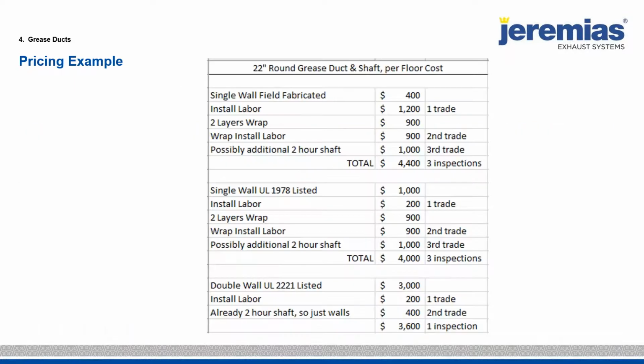The UL listed grease duct manufacturers. Now I want to talk a little bit about cost because that's always important. The person that really benefits, again, is the owner, not the contractors. Now we looked at a 22-inch diameter round system. This had about 12 or 13 different risers going through a very tall building in California. So we actually did some cost analysis that the local contractors agreed with, because when we try to sell our UL listed 2221, we say $3,000 per floor. They say, like, what are you talking about? I can do it for $400 per floor.